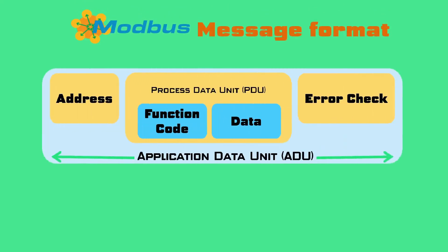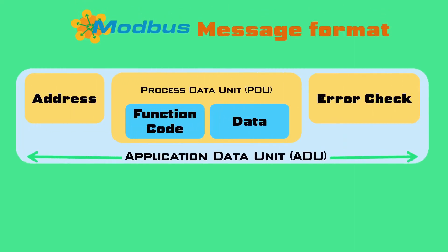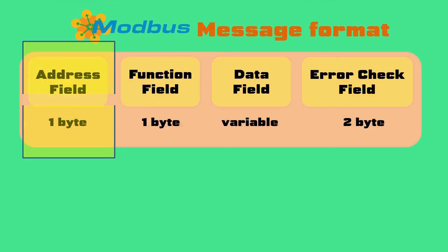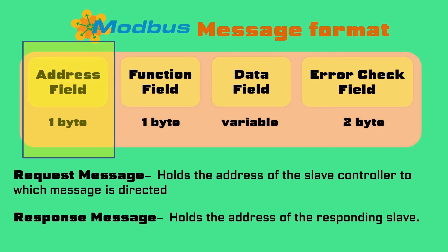A Modbus message frame consists of an Application Data Unit which encapsulates a Process Data Unit. In totality, there are four fields in any Modbus message. The first field is the address field — a single byte of information. In request frames, this byte identifies the slave controller to which the request is being directed. In response frames, this field holds the address of the responding device.